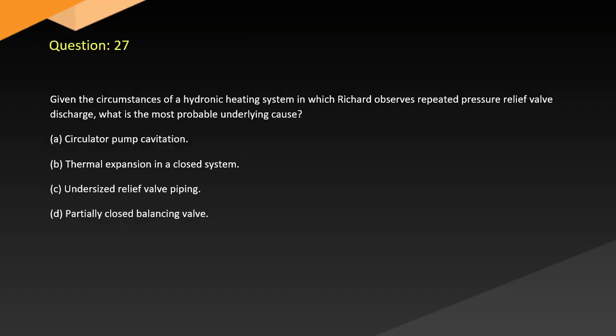Question 27. Given the circumstances of a hydronic heating system in which Richard observes repeated pressure relief valve discharge, what is the most probable underlying cause? A. Circulator pump cavitation. B. Thermal expansion in a closed system. C. Undersized relief valve piping. D. Partially closed balancing valve.